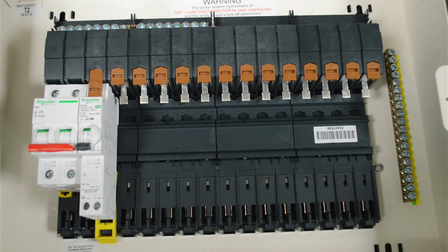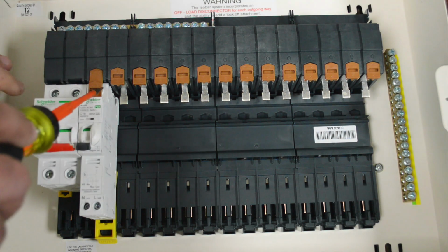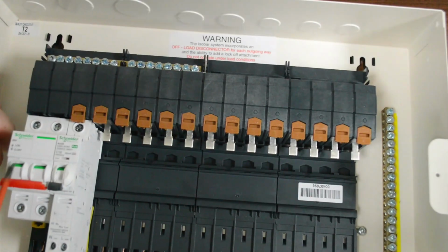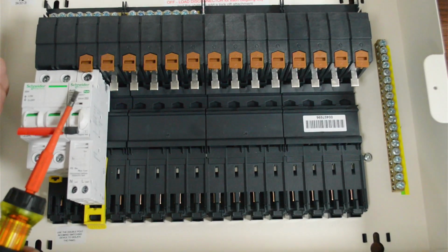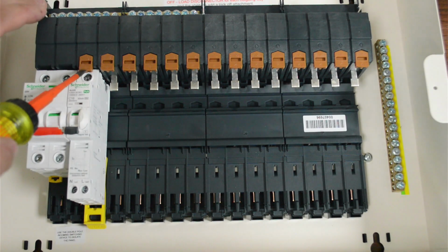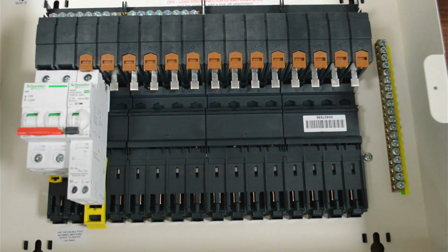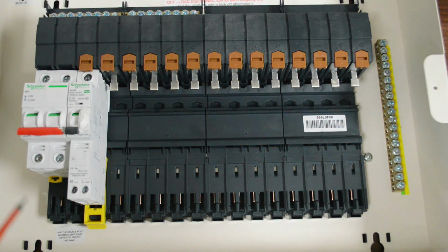That essentially switches this on, so it allows the connection to be made into the live busbar. And again, obviously if you need to remove the RCBO, so it's faulty or you're changing the overcurrent protected device or whatever, this tab pushes back in first, and that would release access. Whoop, knocking everything all over. That would release access to the screw terminal to undo it. Obviously this would be fixed to a wall, so it's not going to be spinning around.